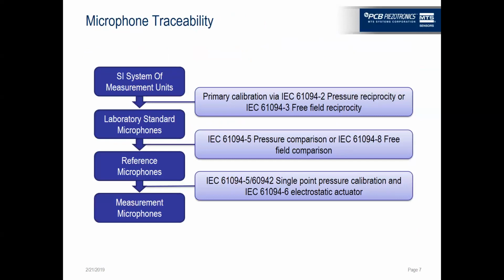factory here, we have both laboratory standard microphones and reference microphones. And then what I do is I'll use the laboratory standards as a measurement check on our reference microphones. And then in production, our reference microphones are used as single point pressure calibration for our measurement microphones. And furthermore, we use an electrostatic actuator in production for most of our microphone models in order to generate our frequency responses.